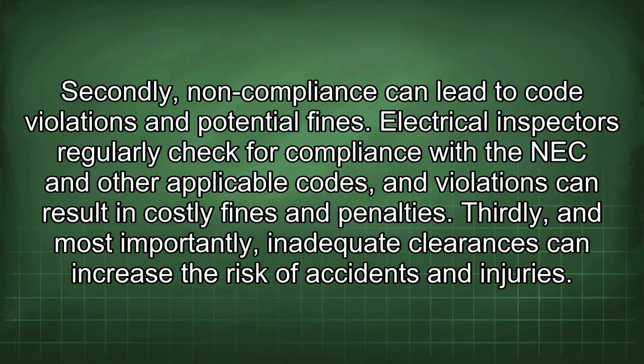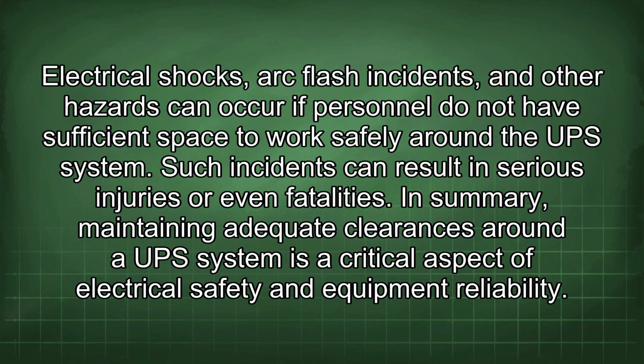Secondly, non-compliance can lead to code violations and potential fines. Electrical inspectors regularly check for compliance with the NEC and other applicable codes, and violations can result in costly fines and penalties. Thirdly, and most importantly, inadequate clearances can increase the risk of accidents and injuries. Electrical shocks, arc flash incidents, and other hazards can occur if personnel do not have sufficient space to work safely around the UPS system. Such incidents can result in serious injuries or even fatalities.